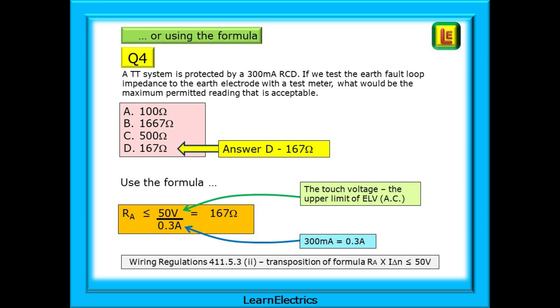50 volts is what we call touch voltage, the upper limit of the ELV voltage range. And 0.3 amps is the same as 300mA. 50 volts divided by 0.3 amps is 167 ohms. Again, answer D.